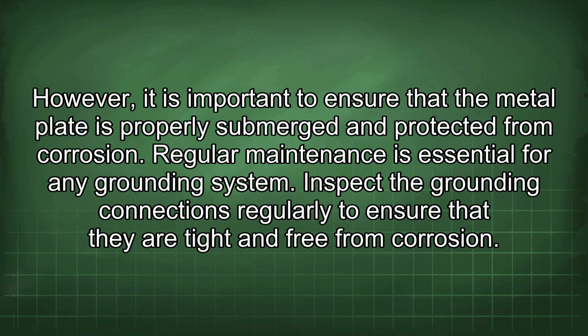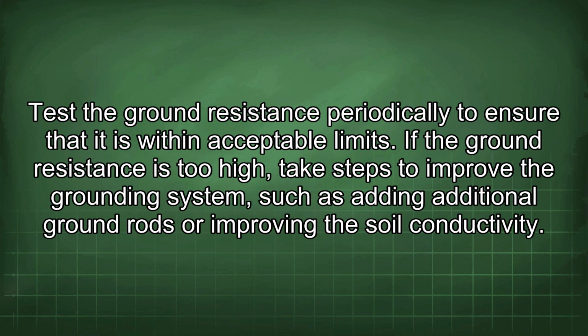Regular maintenance is essential for any grounding system. Inspect the grounding connections regularly to ensure that they are tight and free from corrosion. Test the ground resistance periodically to ensure that it is within acceptable limits. If the ground resistance is too high, take steps to improve the grounding system, such as adding additional ground rods or improving the soil conductivity.